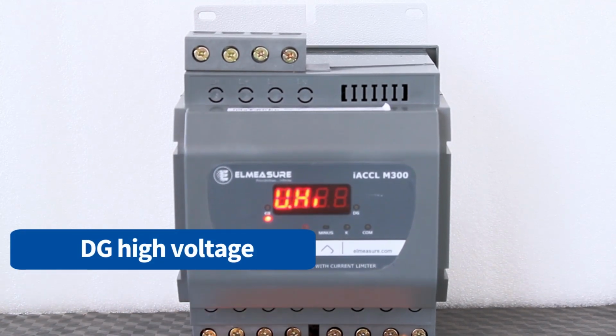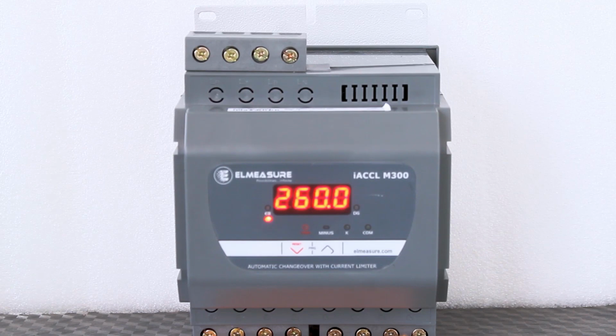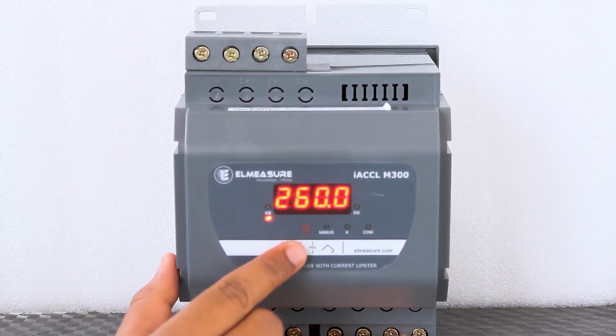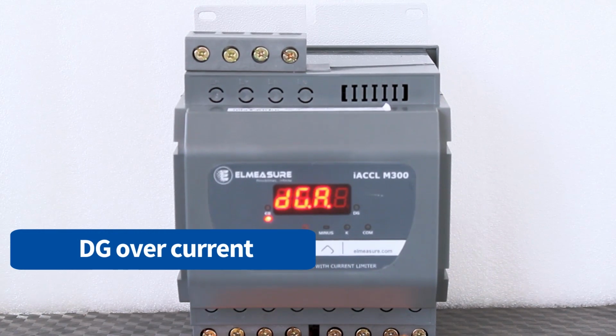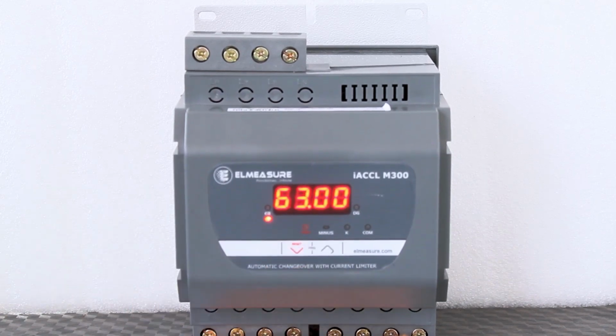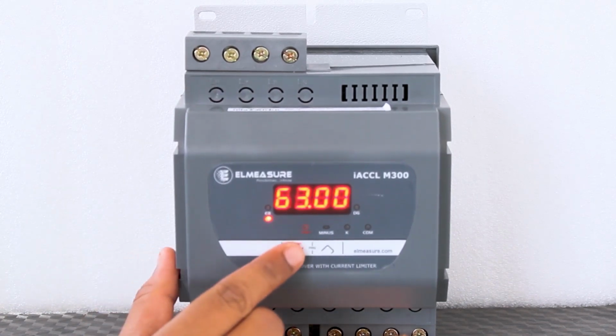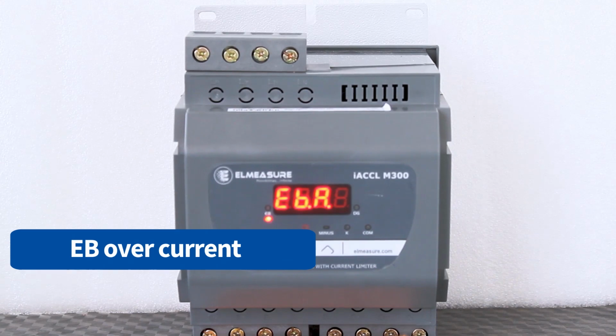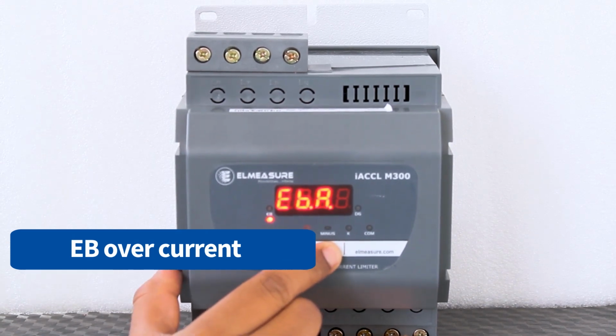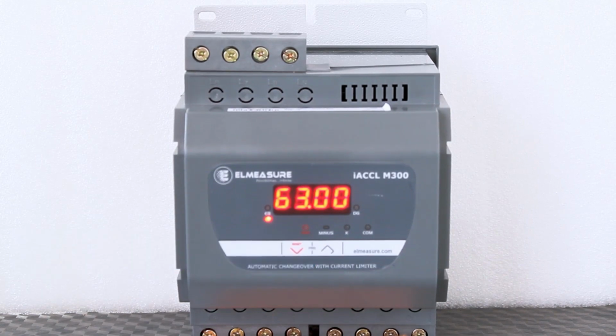This is DG high voltage. The default value will be 260. You can set the values from 240 to 270 volt. This is DG over amps. The default value is set as 63. You can set the range from 0 to 63. This is EB over amps. The default value is set as 63. You can set the range from 0 to 63.